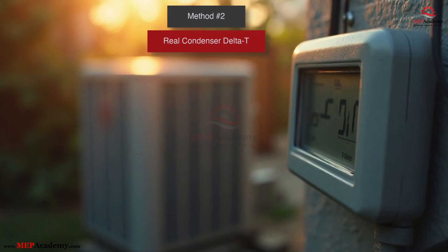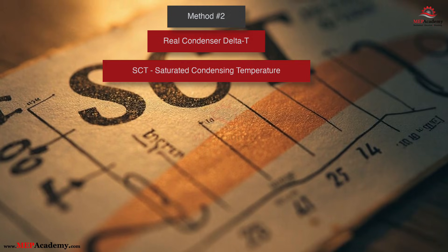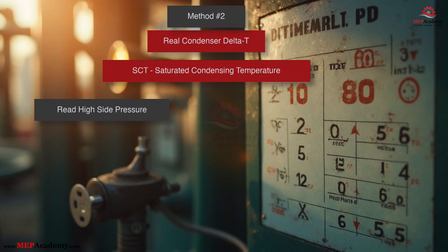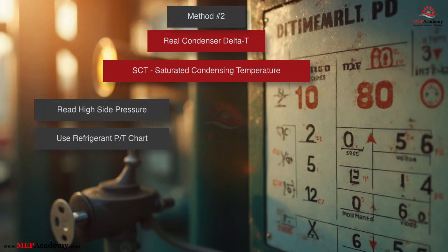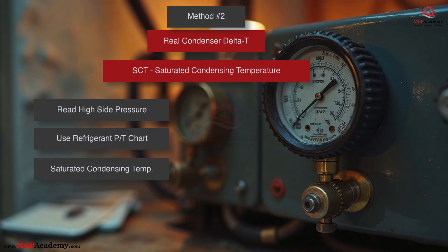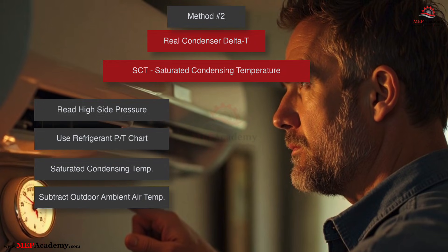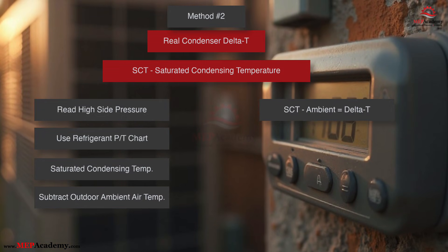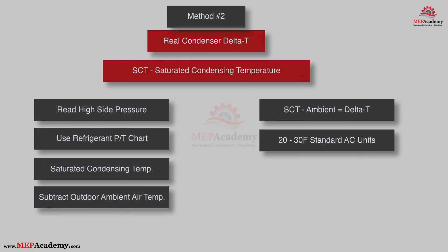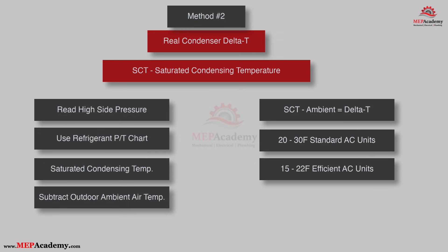Method number two: real condenser TD. SCT — saturated condensing temperature — is determined by reading the high side pressure on your gauge manifold and converting that pressure to a temperature using the refrigerant's PT chart. You hook up your high side gauge, read the pressure, convert to saturated condensing temperature using a PT chart or app, then subtract the entering ambient air temperature. SCT minus ambient equals condenser temperature difference TD. Typical numbers: 20 to 30°F on standard units, 15 to 22°F on high efficiency equipment. Takes two to three minutes and a set of gauges. This tells you the refrigerant's saturation temperature inside the condenser coil — it's a refrigerant thermodynamics measurement, not an airflow measurement.